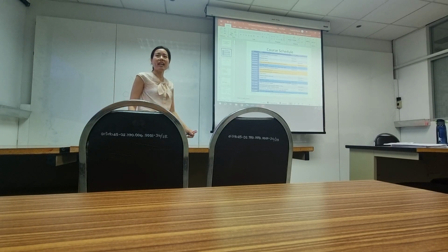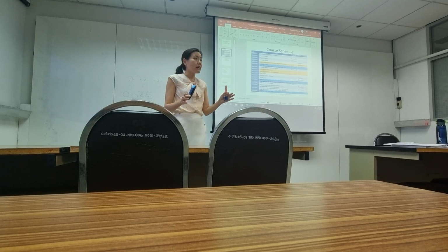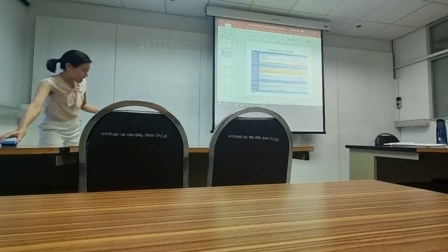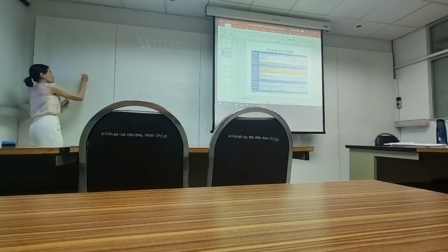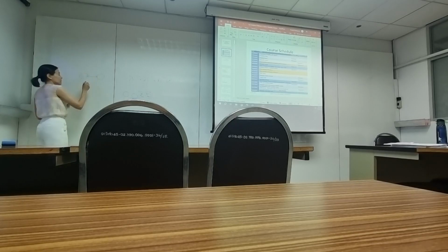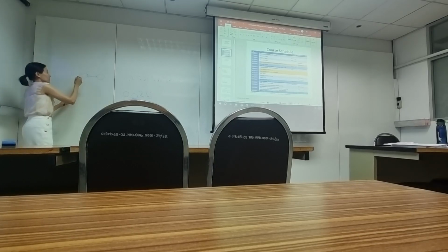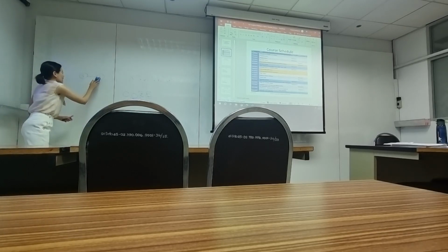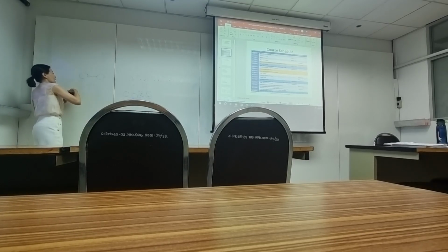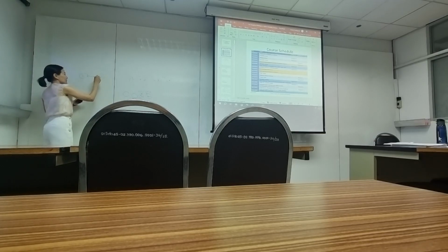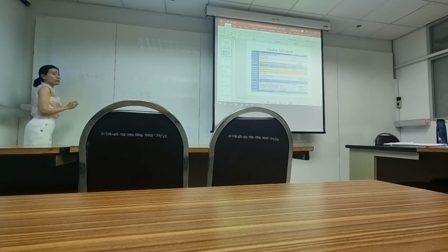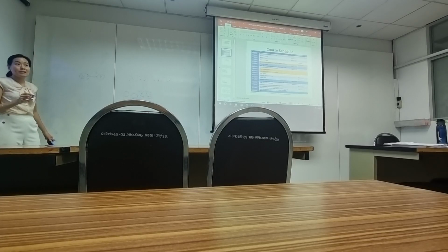From the idea of stochastic process, we look at how we can analyze reliability, which is very simple, right? When we look at reliability, we calculate what? The probability, right? And then I told you that if the things you are trying to look at are independent and have only two states, success and failure, sorry, I use up and down, right? So when the device is up and then the device is down, the device has a failure rate of lambda, the device has a repair rate of mu, then you can find the probability.